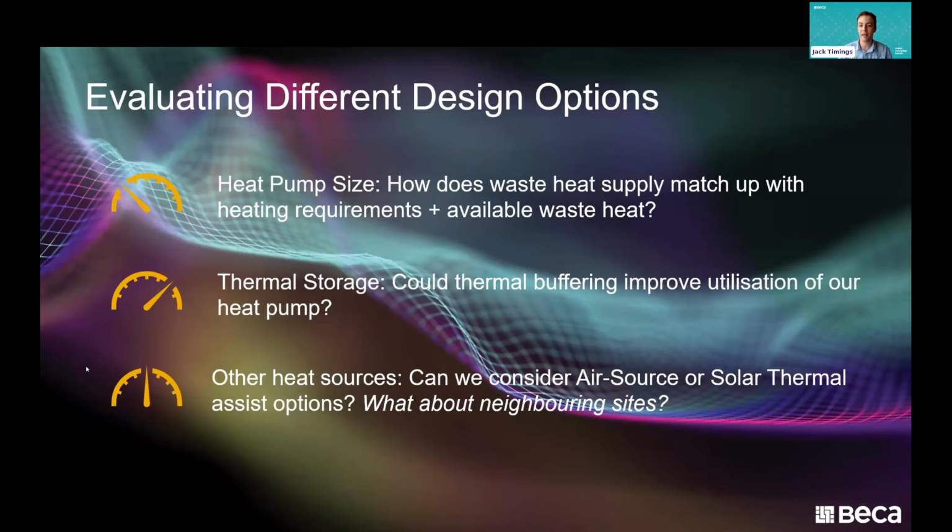And then we had to think about other heat sources as well, right? We discovered that this system was one where we could put in as big a heat pump as we wanted. Effectively, there was so much heat demand at that site that we weren't ever going to be able to totally get rid of the gas with just the refrigeration plant. So we had to start thinking about other options.